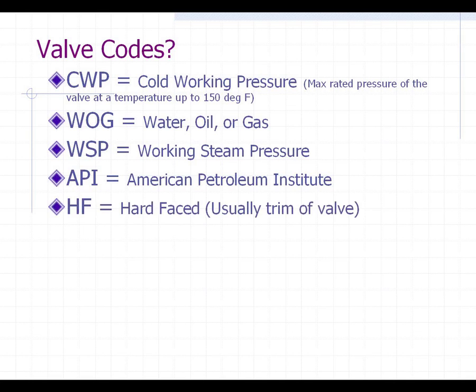HF — especially in the power industry, you will see the trim of the valve described as hard faced. If a valve is made of carbon steel, the disc and seat inside the valve would typically be a 400 grade stainless steel. To harden it further and protect the trim from erosion due to velocities, they weld on an overlay of most commonly stellite, though tungsten carbide is also used for hardness. That's what HF stands for when you see it in the trim specification.